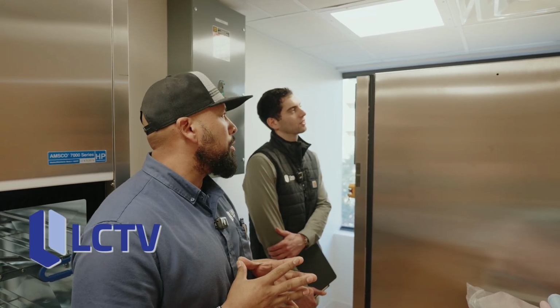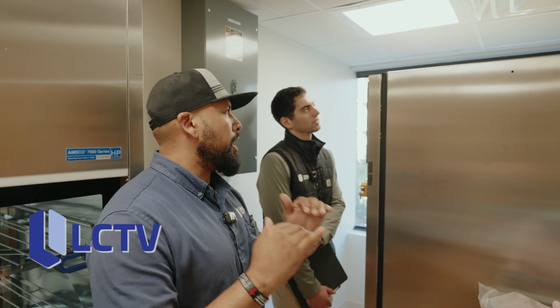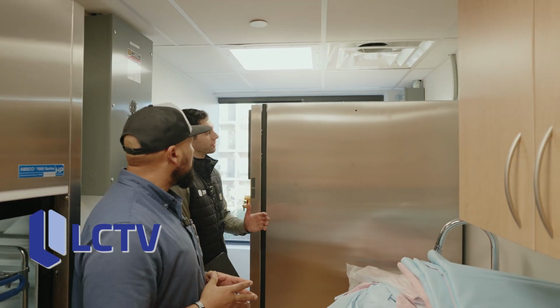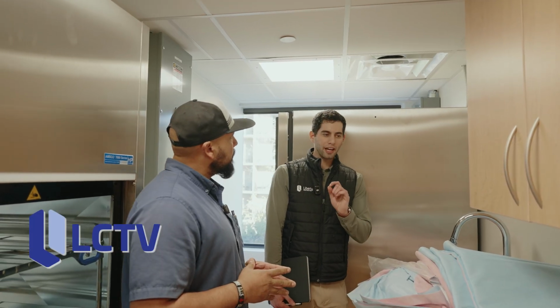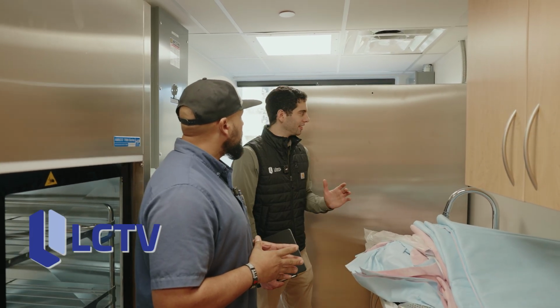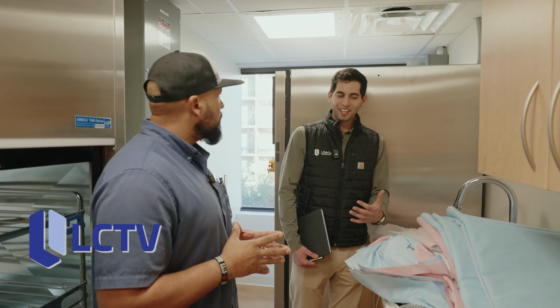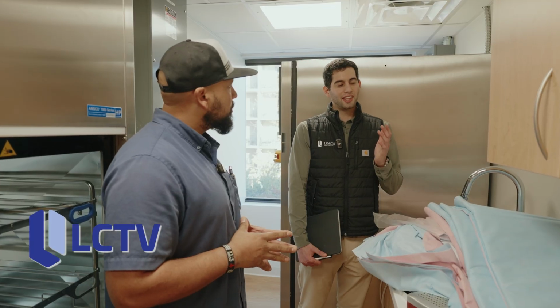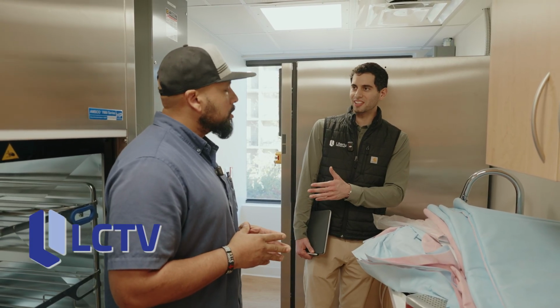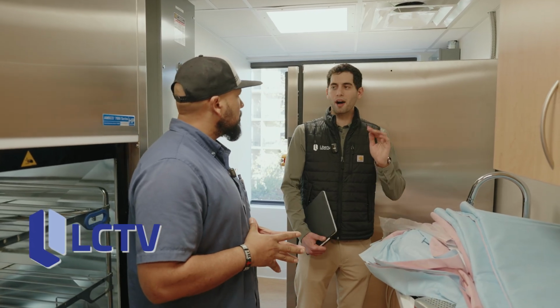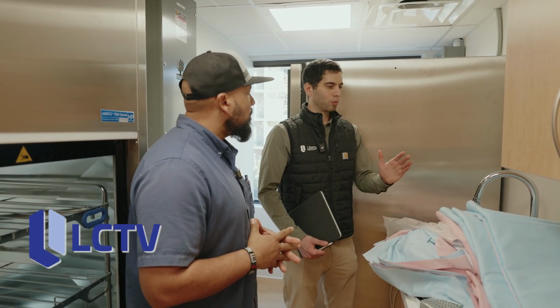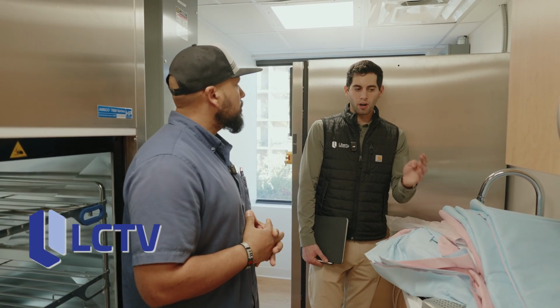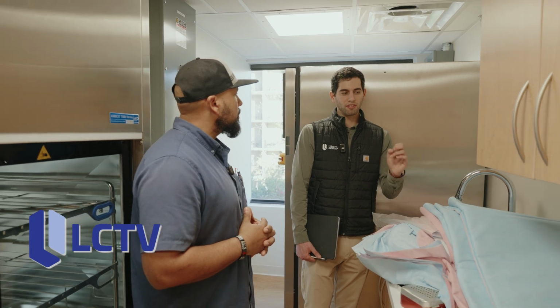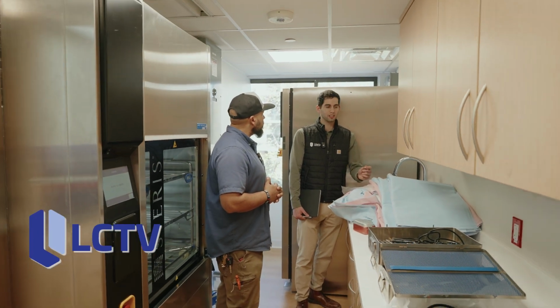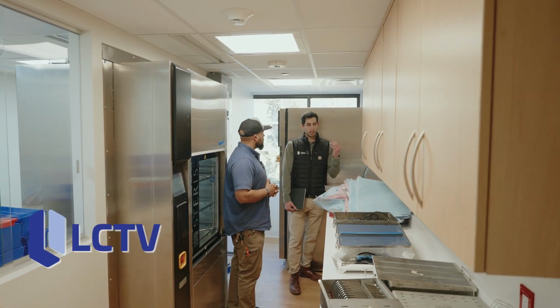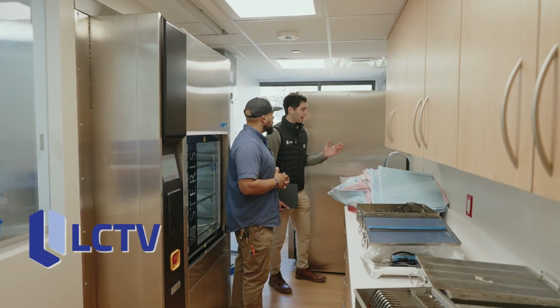So having that diffuser right above it is definitely going to help a lot in maintaining the temperature in this room. Once the new units are in and all the equipment, I think you touched on a really good point. All the equipment has to be functional, because it's not until you see how much heat is generated by the third-party equipment that isn't furnished by us, in some cases not even installed by us, that you can really do the TAB report, which is testing, air balancing. We don't want to just worry about the CFMs and positive pressure differentials and then leave it at that. If we calibrate the units, which are very sensitive, and it's all third-party calibration, and even the thermostats are very specific to just this unit that we are fabricating now, because there's gas reheat and there is a specific BAS system that we're integrating with, you don't want to have to do that multiple times.